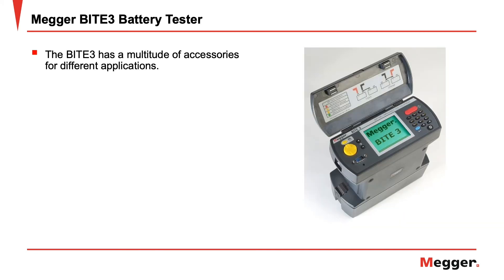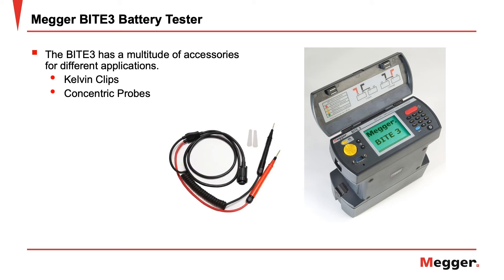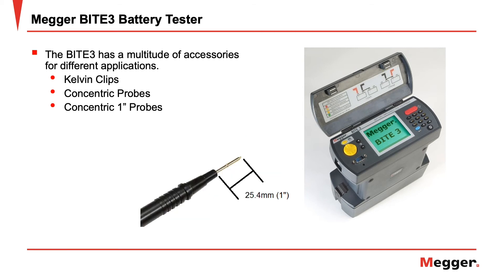The BITE3 also has a multitude of accessories for different applications. Kelvin clips allow for simple hands-free testing, ideal for battery strings with terminals that can be easily clipped to. Concentric probes allow for testing of batteries on strings that have protective battery caps — there's no need to remove the caps, simply access the batteries through the access hole. The 25.4 millimeter or one-inch concentric probe allows for measurements of batteries and strings with even the deepest access holes.